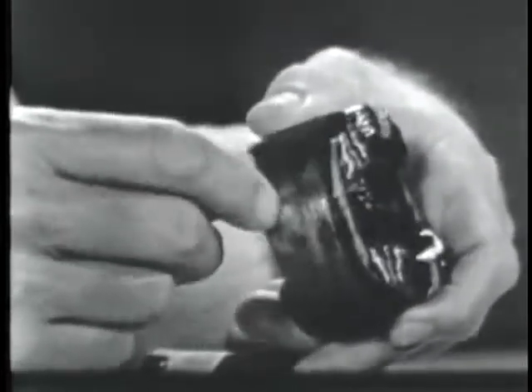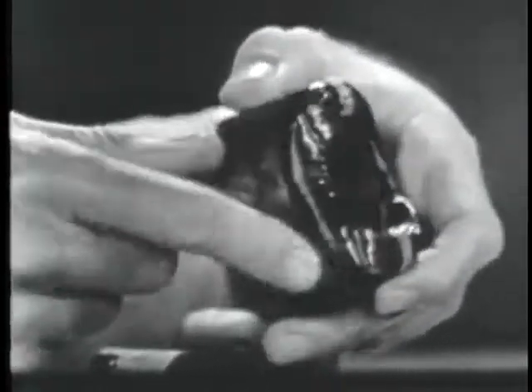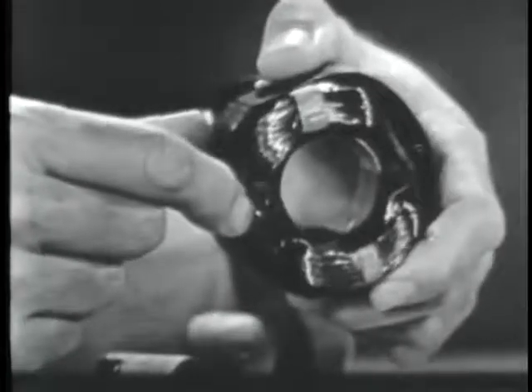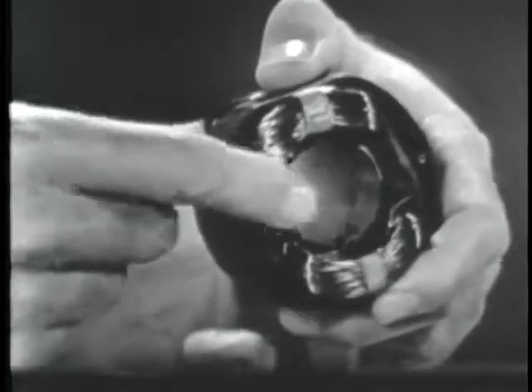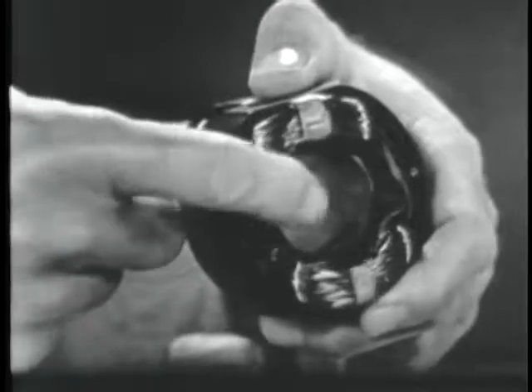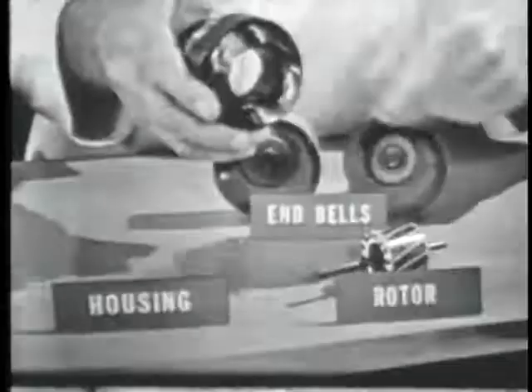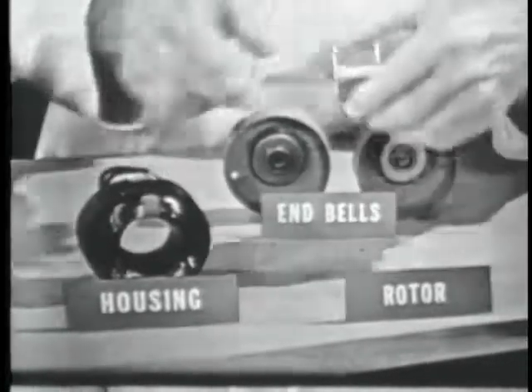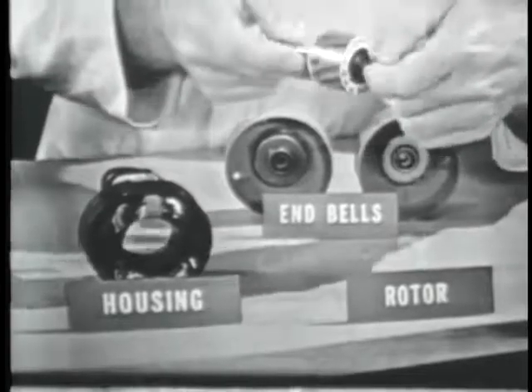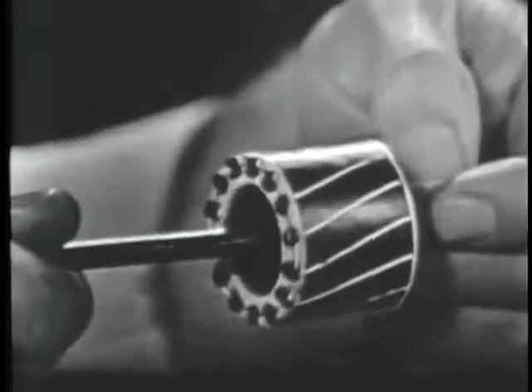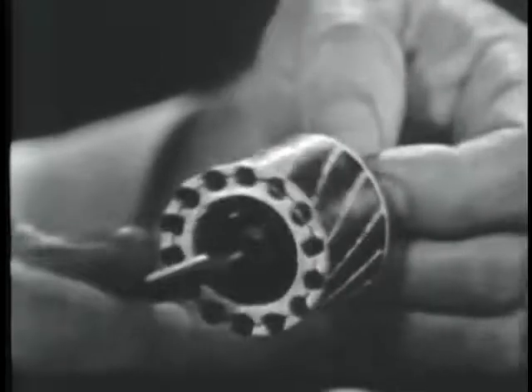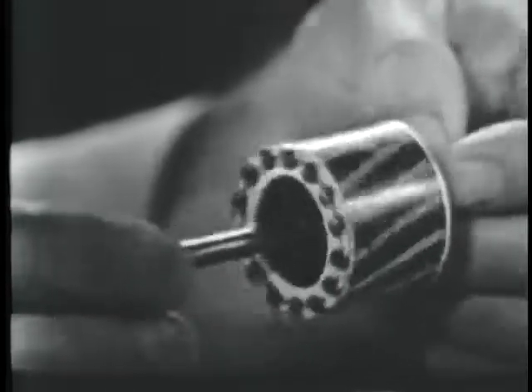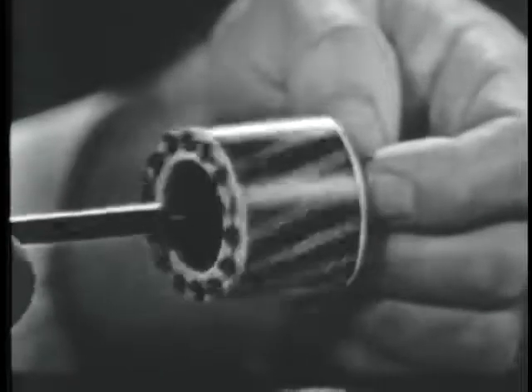Now notice the simplicity of construction. We have the stator field windings, the iron core. Very, very rugged and very simple. Inside the stator field windings, the rotor. Let's take a look at this rotor. All right, the rotor has no commutator, no slip rings, and no wire windings. It doesn't look at all like the rotor used in DC motors, does it?